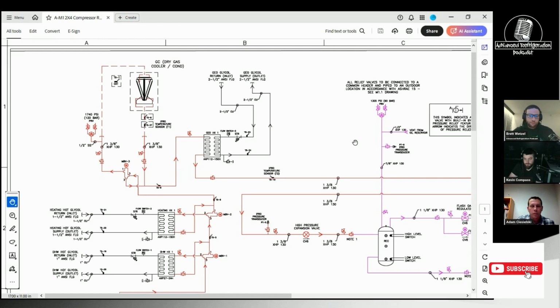A little bit. There's several. We have several units out, and the biggest challenge that I have with that is just implementing it to go in, cut in and cut out, because it creates a very large upset in the system, and it often doesn't recover from it. If you split the gas cooler, essentially now you just double the mass flow through the constant one. That's going to immediately affect your drop leg, and the high pressure valve responds immediately and closes.